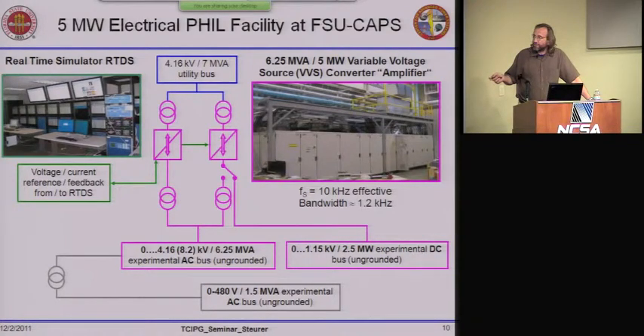In AC mode, we can go up to 6.25 MVA at 4.16 kV, where we completely control the waveform on that bus and connect pieces of hardware to it. We can step that down to 480 volts for low voltage equipment. And half of that system is configurable to become a DC source or sink, which allows us to do experiments up to 2.5 megawatt at a kilovolt level in the DC regime.